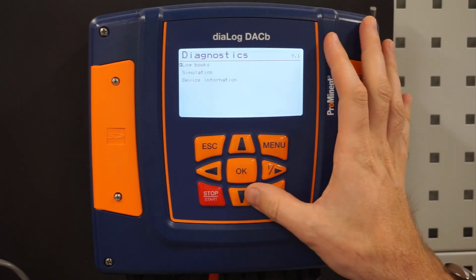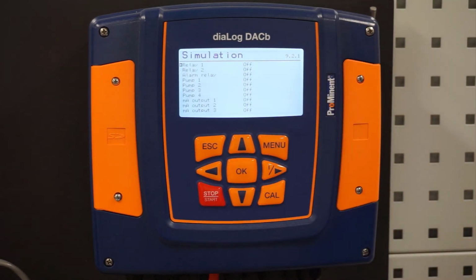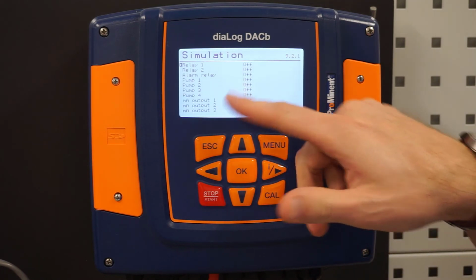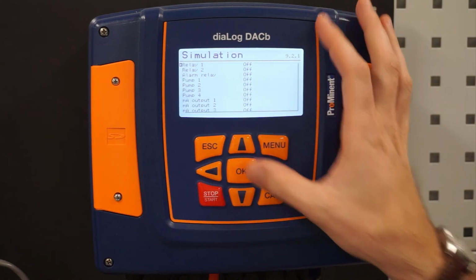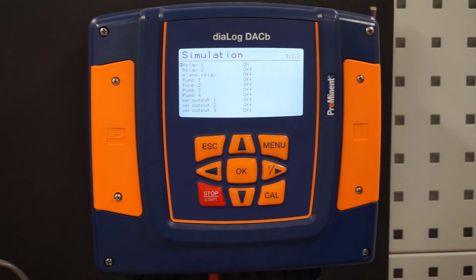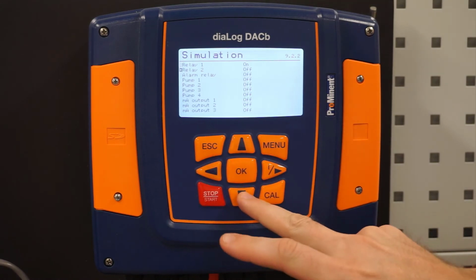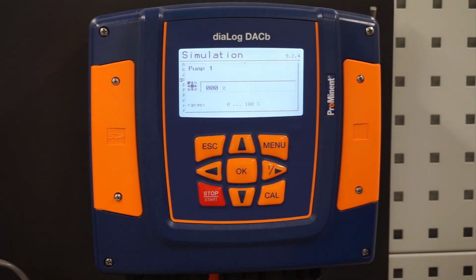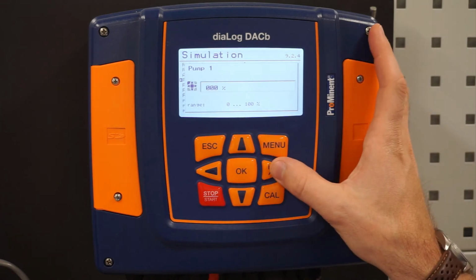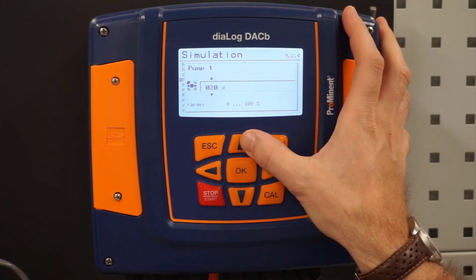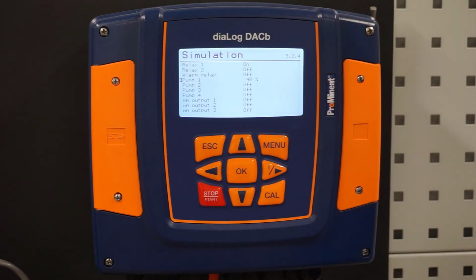One of the last things to show you in the diagnostic menu is going to be the simulation. This is a nice feature that we can use during startup. So you can see I can initiate my relays. So my relay 1, I can go on and turn it on. That will change the state of the relay, and you could tell the operator that they should be expecting to see that signal wherever they have it wired. At the same time, if we have pumps going to those digital outputs, the frequency outputs, we can simulate the pump running at maybe 40% speed.